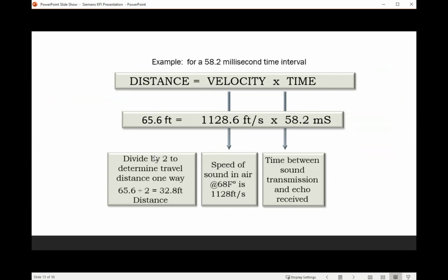But we're only trying to measure the distance to the media and not the distance to the media and back. So we have to divide by 2, and that gives us 32.8 feet. So that's how our distance is calculated using ultrasonic and time of flight.